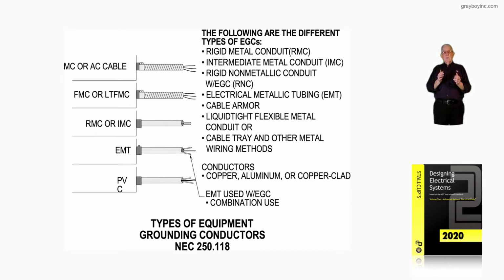Now we would reference 310.10 and 310.6. If you review 310.10, then for the equipment ground, 310.10(B) would refer you to 250.119, say, for color coding or identification. 250.118 now would be used for the grounding scheme that you select.